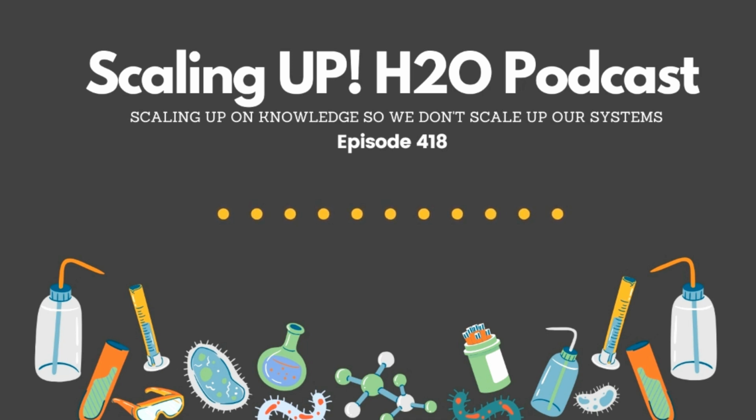Today's question is, what do you call the large diameter tube in fire tube boilers, where the combustion of fuel takes place? It is called a Morrison tube. It may even be corrugated to enhance strength, heat transfer area, and promote turbulence in the combustion gases.